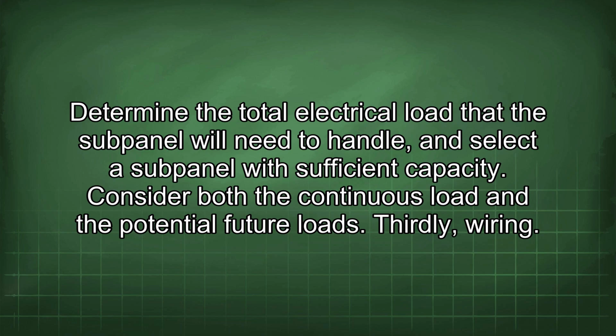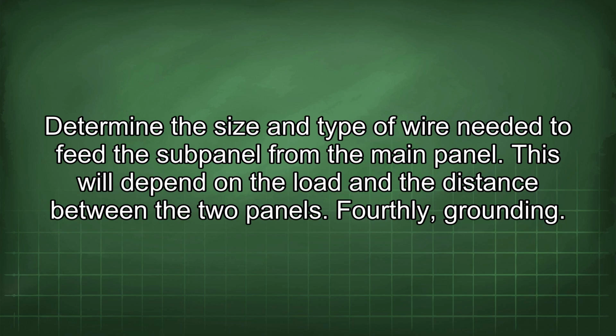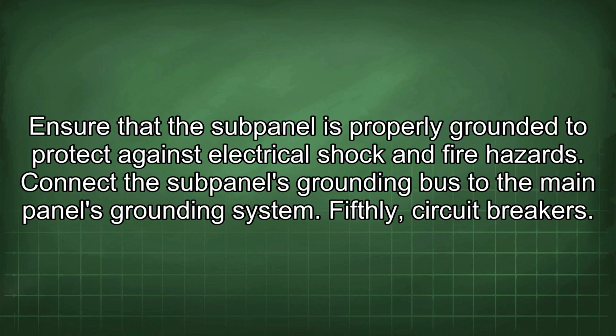Consider both the continuous load and the potential future loads. Thirdly, wiring. Determine the size and type of wire needed to feed the subpanel from the main panel. This will depend on the load and the distance between the two panels. Fourthly, grounding. Ensure that the subpanel is properly grounded to protect against electrical shock and fire hazards. Connect the subpanel's grounding bus to the main panel's grounding system.